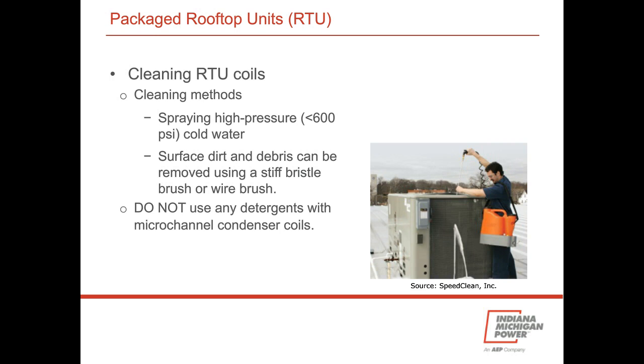And what's a proper method for cleaning coils, particularly condenser coils? Typically it's done with wet vacuuming using high-pressure cold water. Recognize that the coils collect dirt on the side where the air enters, generally outside. And so the high-pressure water pushes dirt out the same way it came in. Now, typically you want to do this using professionals because those aluminum fins bend pretty easily if you spray at the wrong angle. And sometimes hot water and steam are used to clean coils. Generally, surface dirt and debris can be removed using a stiff bristle brush or wire brush. A lot of companies use biodegradable detergents as the safest coil cleaners. However, sometimes you have to go to higher strength alkaline or acid cleaners. And so it needs to be done, and it needs to be done right. Hiring a professional is probably a pretty good idea.